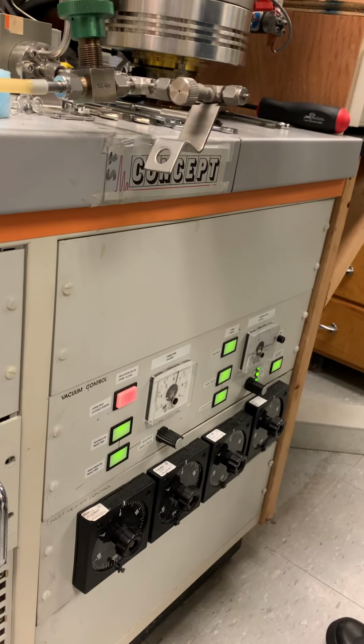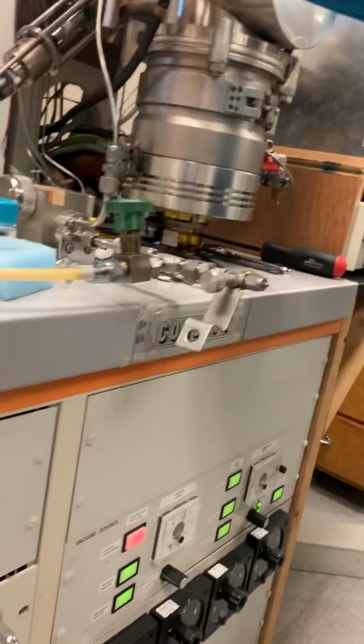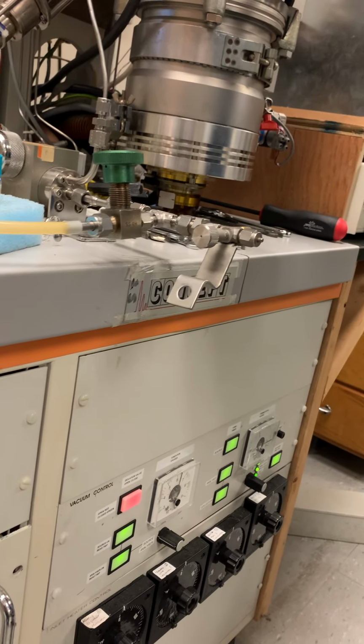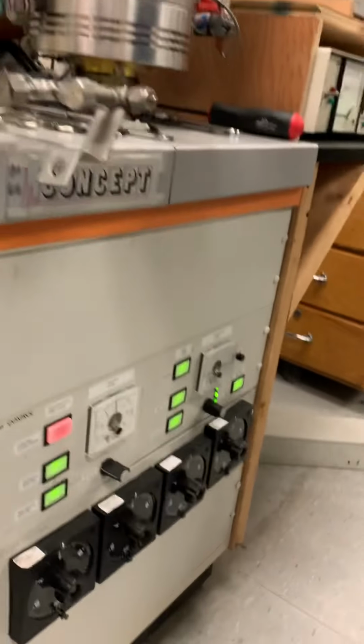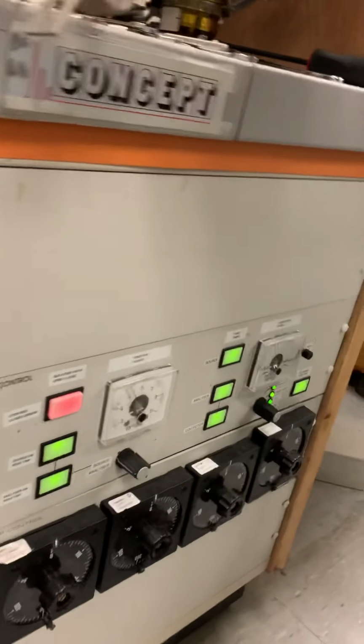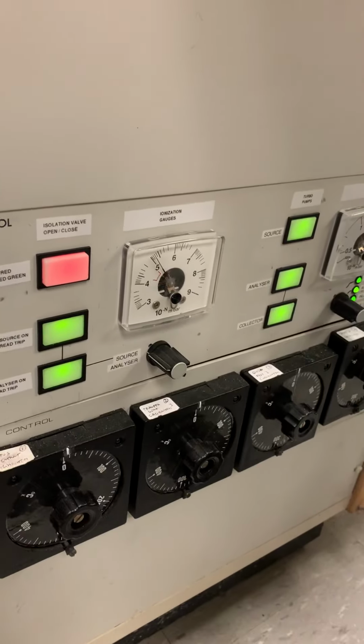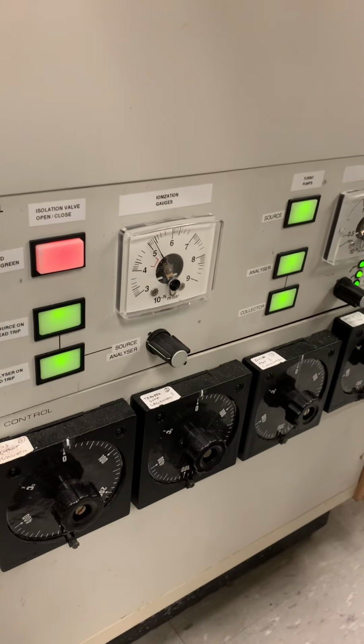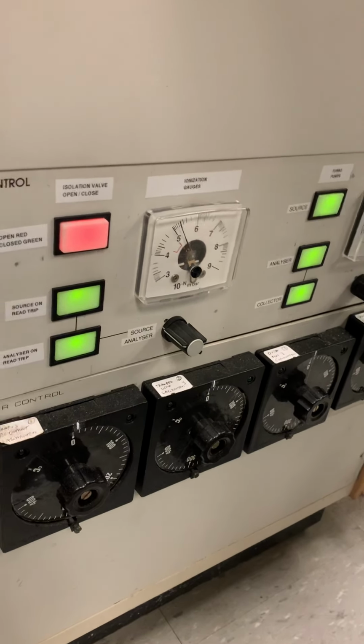ion gauge. So very carefully open it, and with very volatile samples you need to be careful because they will already be in the gas phase. It's just very carefully keeping my eye on that, and you get to the point where it won't go up anymore and you can actually open the gate valve up completely.